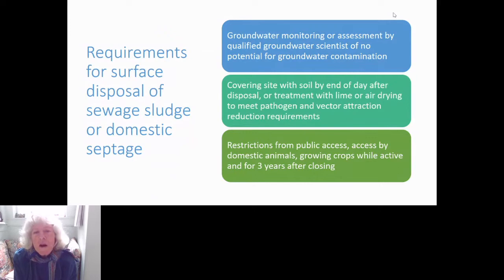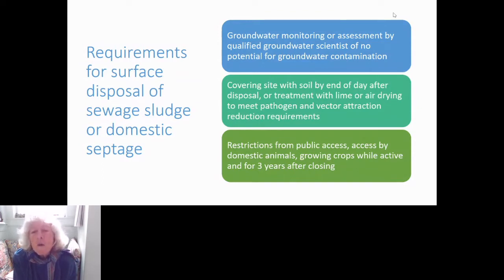Another requirement is to meet vector attraction reduction requirements, which means preventing fleas, rats, and other vectors from getting in. The most common way to do this is to cover the site with soil by the end of each day after the septage or sewage sludge has been disposed. Or you can treat it with lime and raise the pH to 12, or you can air dry it in a drying bed to the point where it's been dried for several months and there's no longer a vector attraction reduction issue.